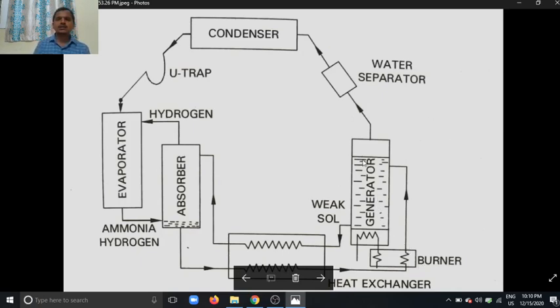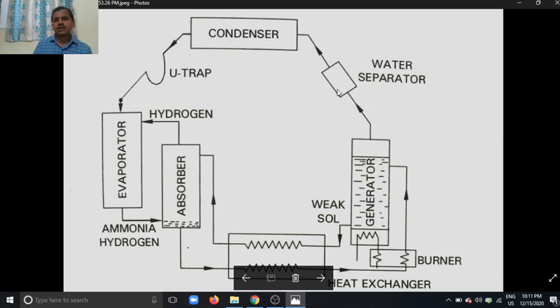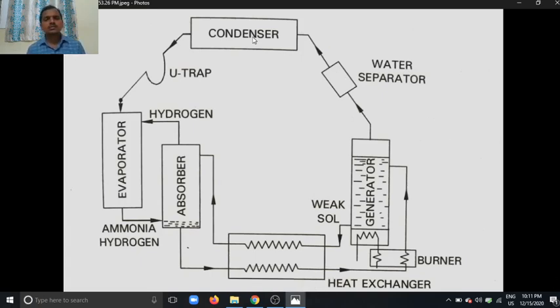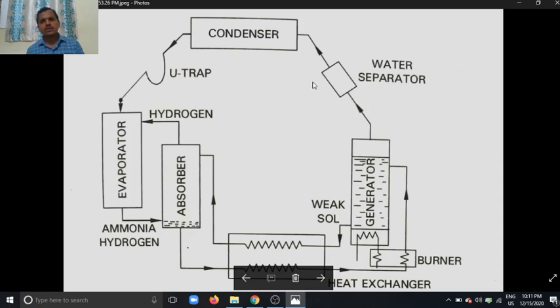The burner supplies heat to the generator. The generator generates high pressure and temperature, and due to that high temperature and pressure the vapor ammonia is separated from the water. This vapor ammonia goes to the condenser through the water separator, which separates any water particles from the ammonia. So the main components are: condenser, water separator, U-trap, evaporator, absorber, heat exchanger, and generator.